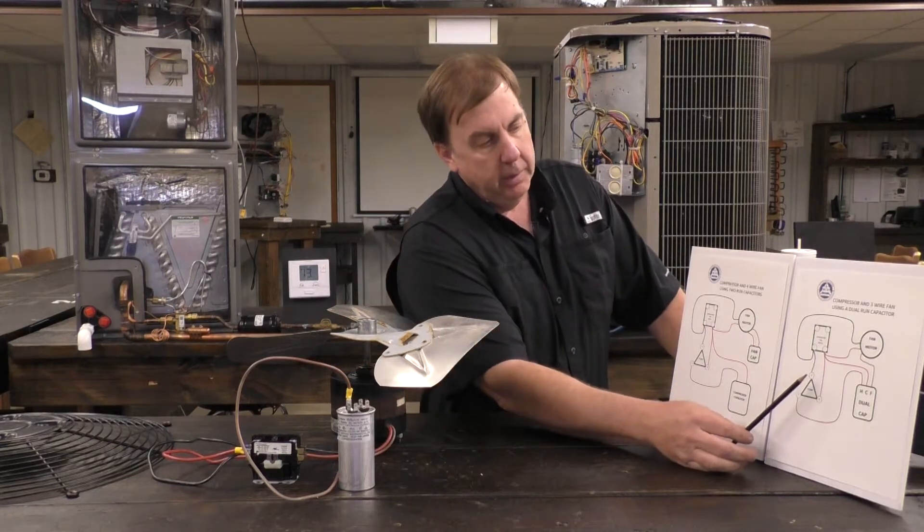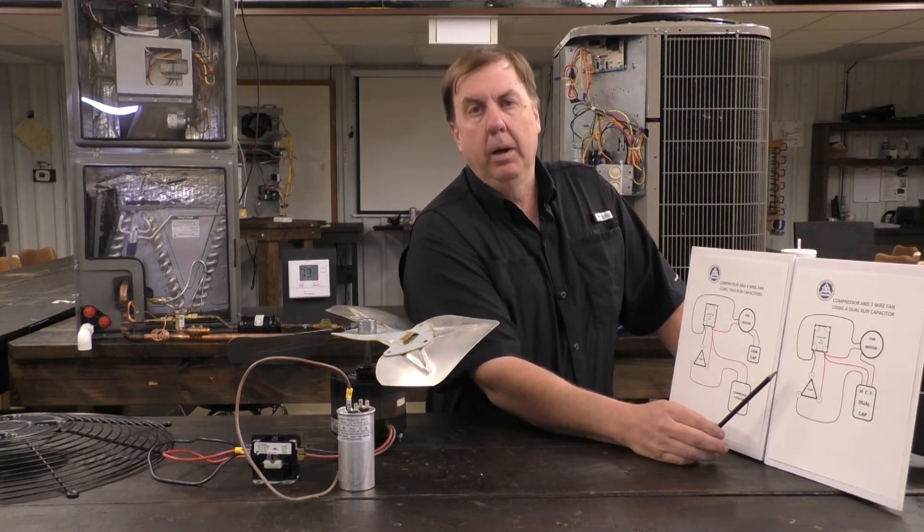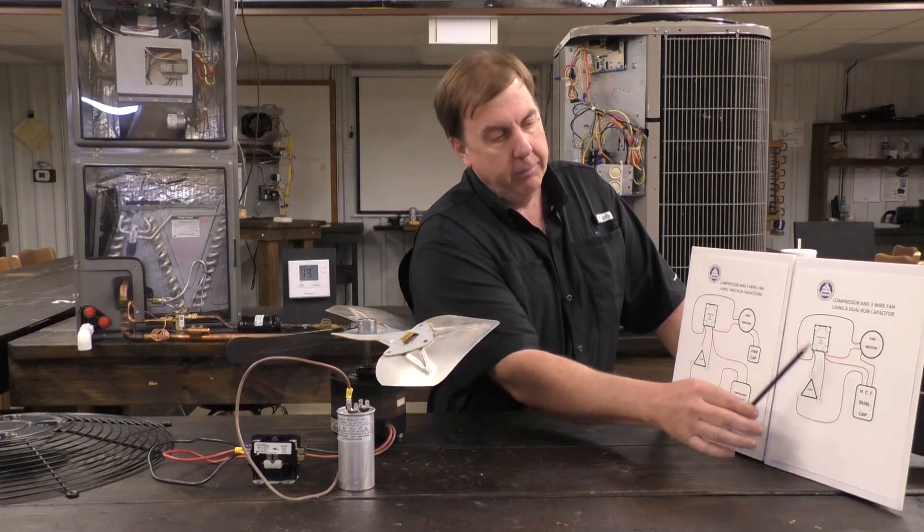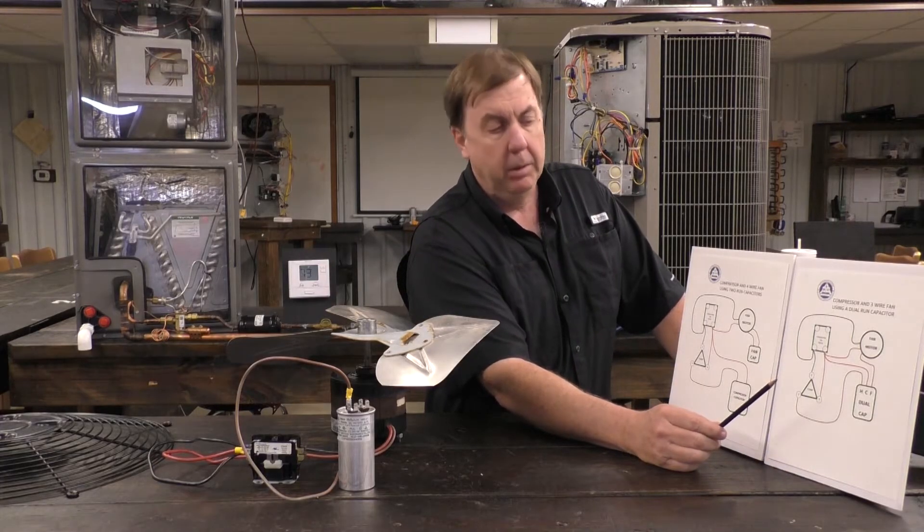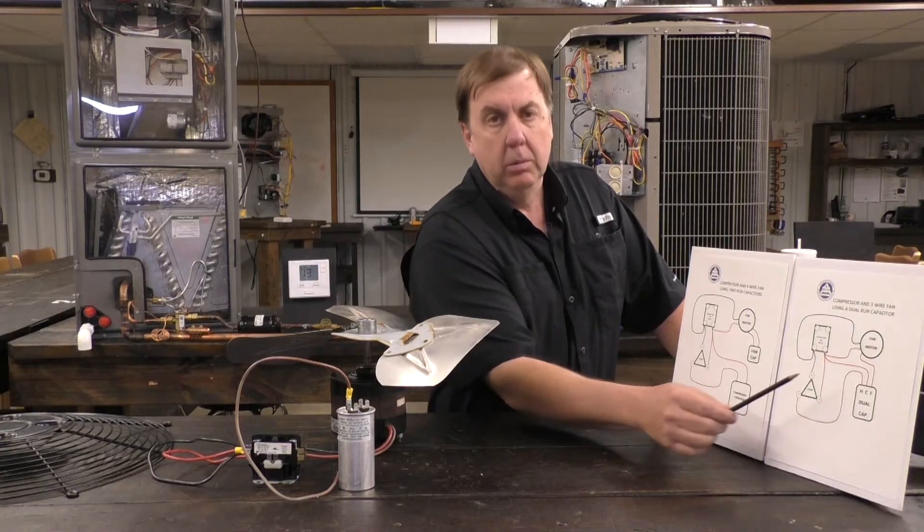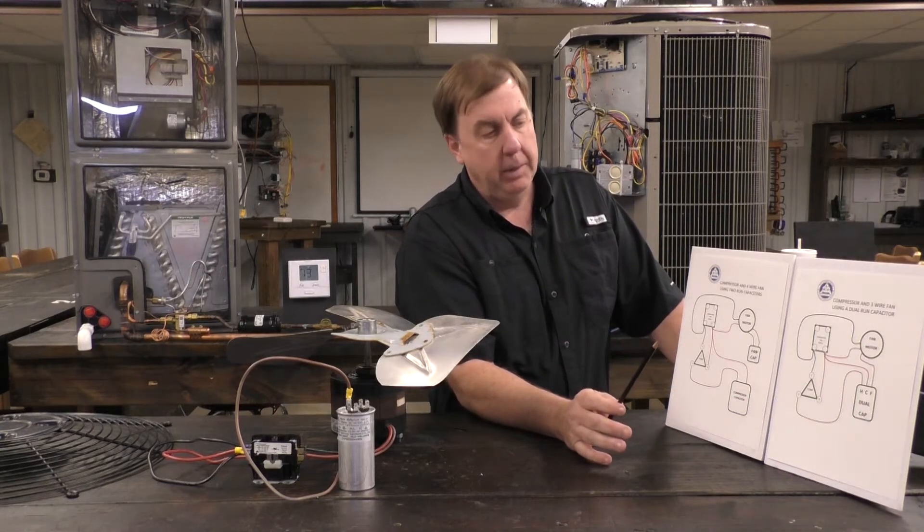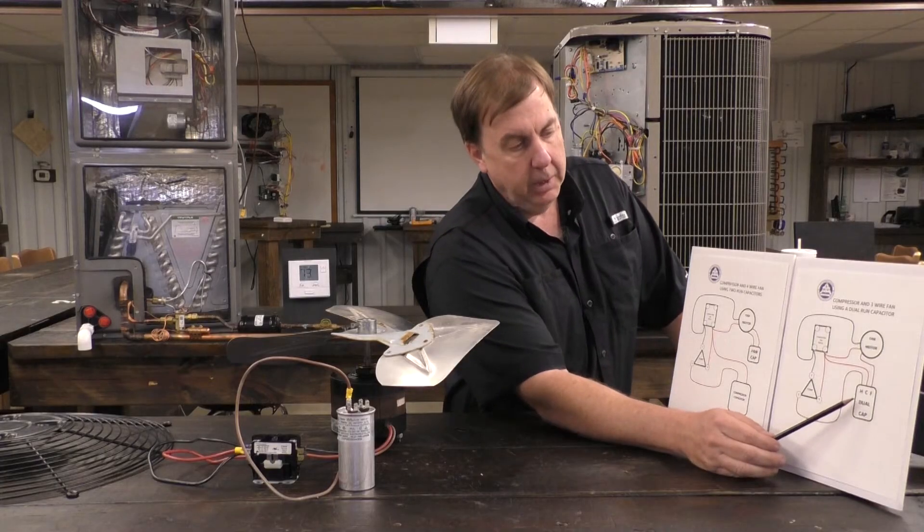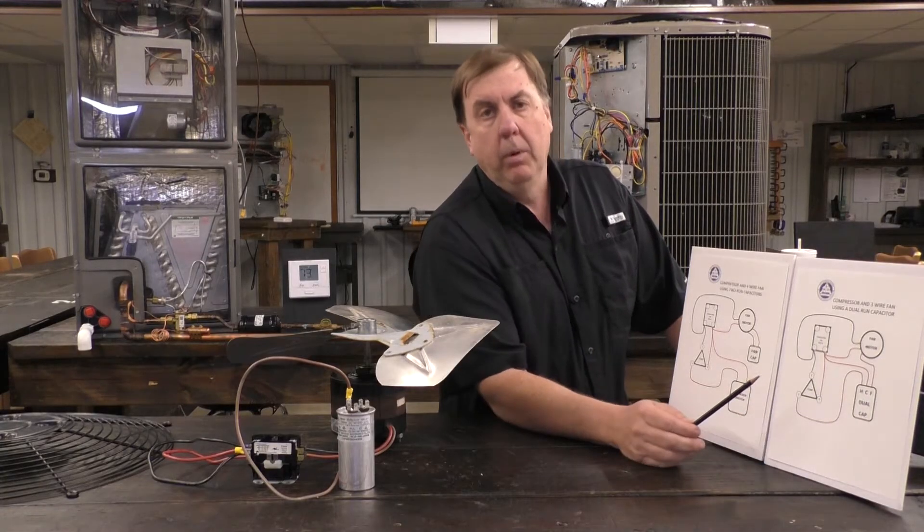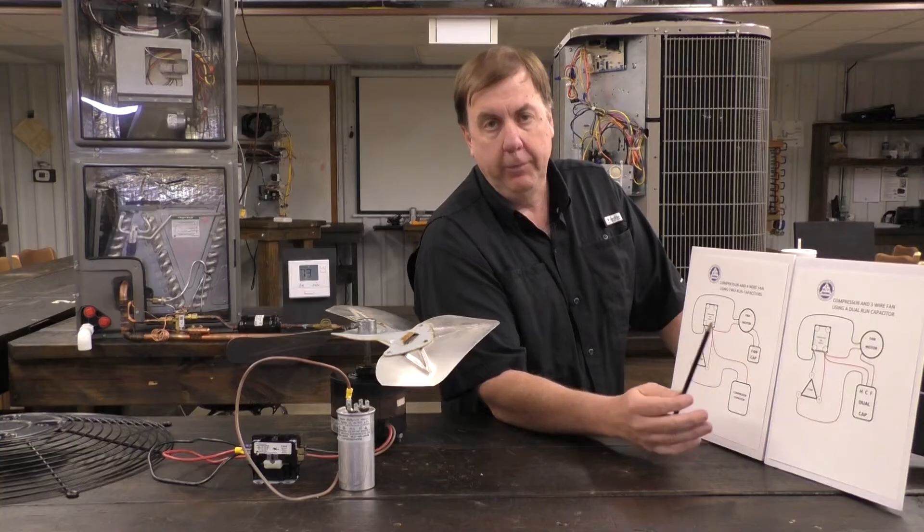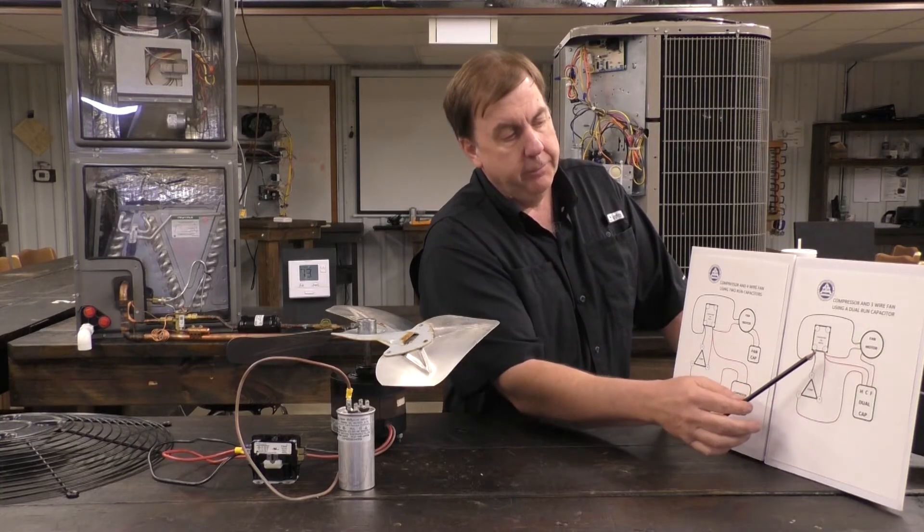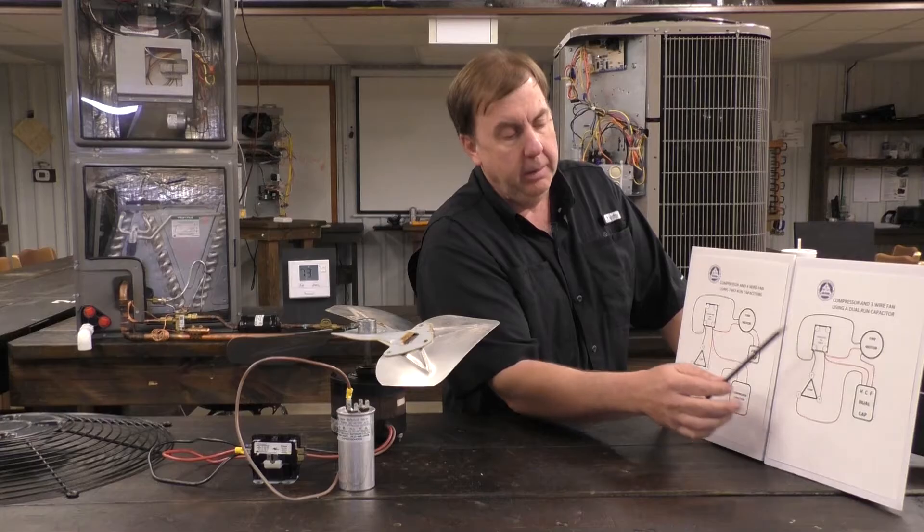Right here we have the normal 3-wire OEM motor, that's what we would have right here. So if you notice, typically it's a 3-wire motor because we have a dual cap, meaning the compressor and the fan both use the same cap. So because it's a dual cap, we only need one wire going to the cap, that's the wire from the fan motor, that's the third wire. The other two wires on the fan motor go to the contactor here and here.